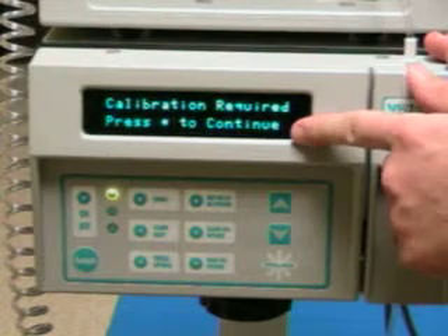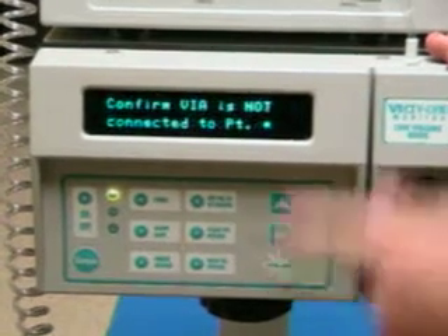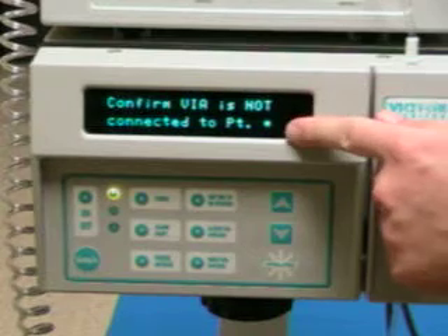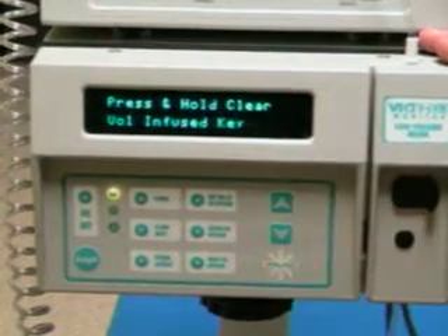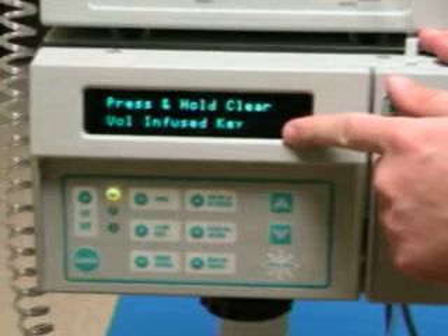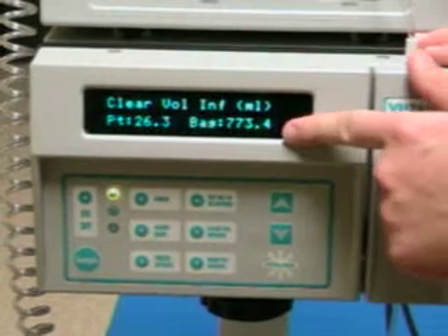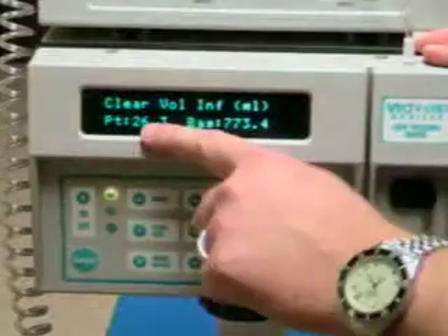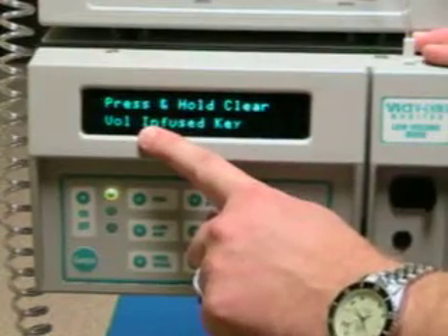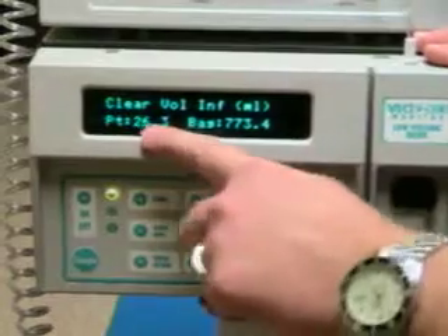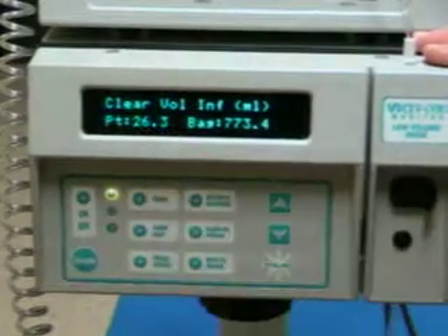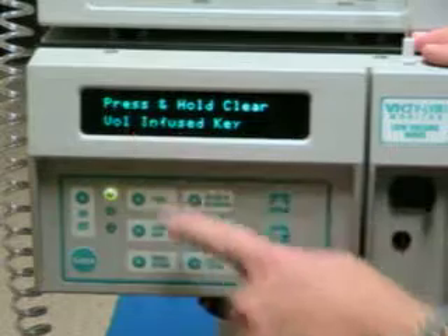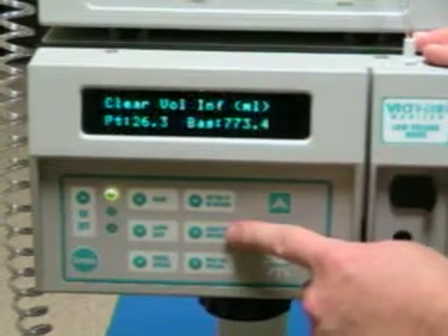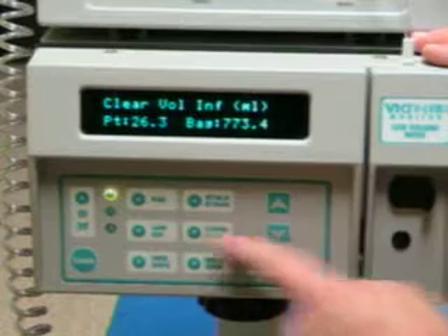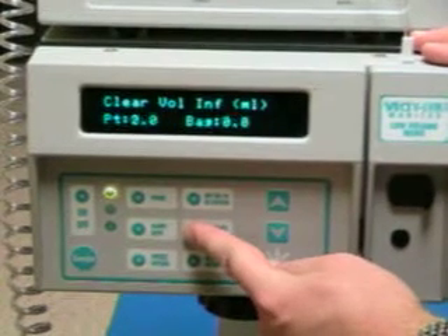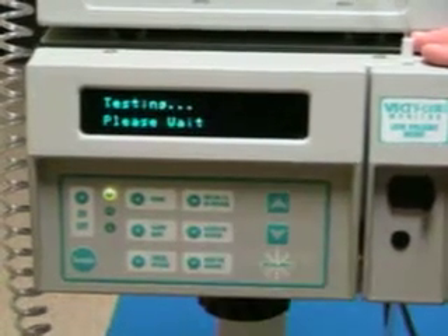Calibration required, press star to continue. Confirm that the IV is not connected to the patient. Press and hold, clear volume infused. So now after every shift, what most hospitals do is they track the amount of volume infused to the patient. It's reading here from the last patient, 26.3 went to the patient in a certain amount of time. What we're doing at the first of the calibration is starting off with 0. So we'll hit clear volume infused here, hold it down till it hits 0, and then we'll let it go.